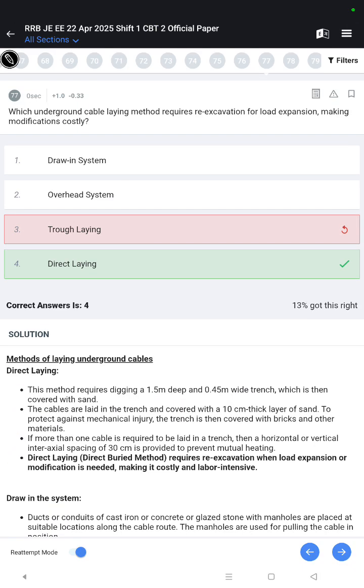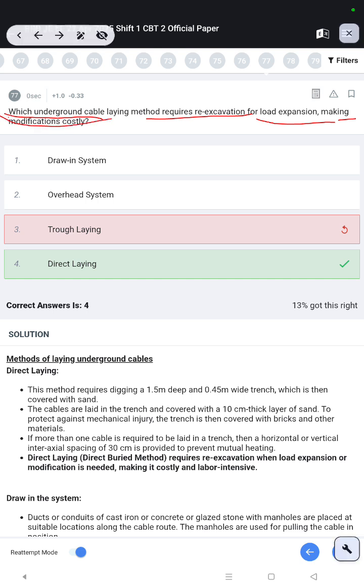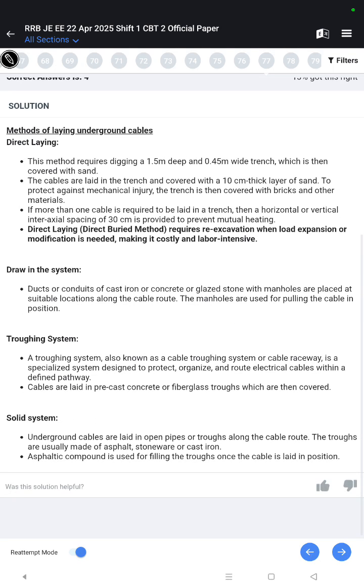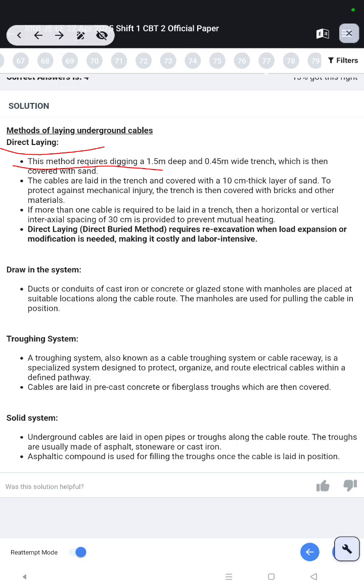Which underground cable laying method requires re-excavation for load expansion, making modifications costly? Direct laying. This method requires digging a 1.5 meter deep and 0.45 meter wide trench, which is then covered with sand.